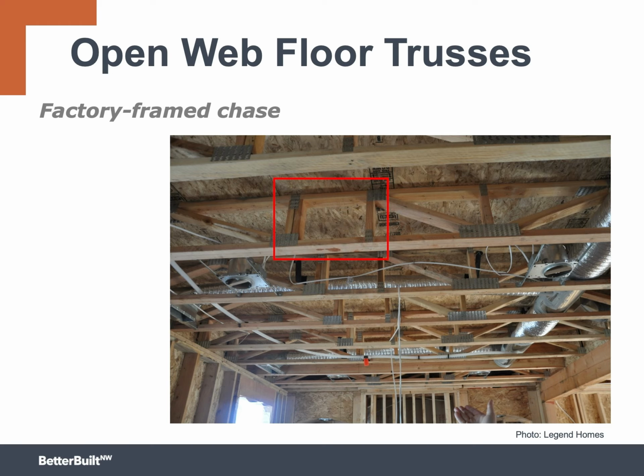So you have to be careful that other stuff like recessed lights, large diameter electrical wires, or gas pipes are not installed in this space. Be sure to coordinate with the other trades. The fire code may require that this floor cavity be compartmentalized into different sections, each one being no greater than about 100 square feet. So check with your fire code about how expansive this open plenum can be.